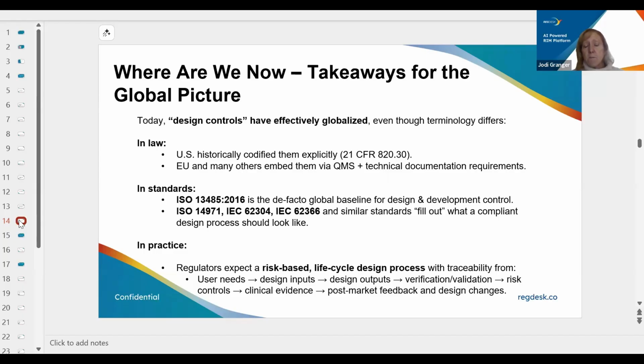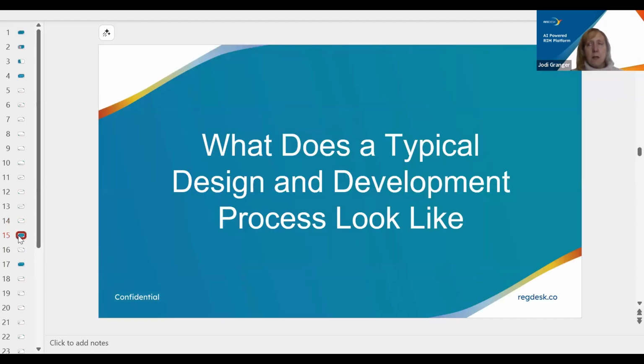So in practice, all regulators, regardless of the terminology they're using, are moving more toward a risk-based life cycle design process. It starts out with customer user needs so that you can create your design inputs, confirm those inputs with outputs, and verification and validation testing, all the risk controls, clinical evidence. And then a very important part of the process is after you market, all that post-market feedback that you receive needs to be assessed to determine whether design changes are required. So that's kind of the history of design controls and how they came into play in the medical device space.